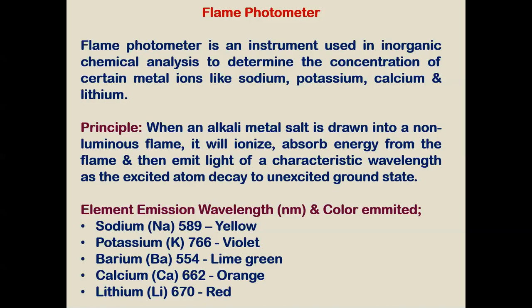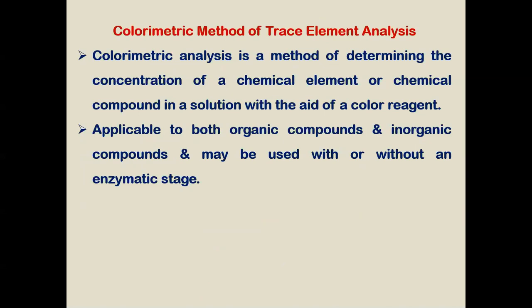The concentration of certain minerals — sodium, potassium, calcium, and lithium — can be determined by flame photometry. The principle of the flame photometer is that when a metal salt is drawn into a non-luminous flame, it will ionize, absorb energy from the flame, and emit light characteristic of that element. As the excited atom decays to its unexcited ground state, different elements emit different wavelengths and colors: sodium at 589 nm (yellow), potassium at 766 nm (violet), barium at 554 nm (green), calcium at 622 nm (orange), and lithium at 670 nm (red).